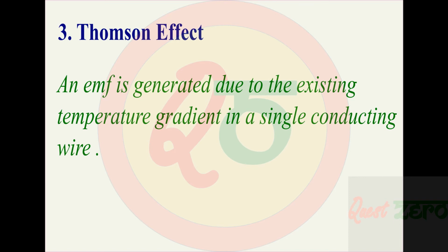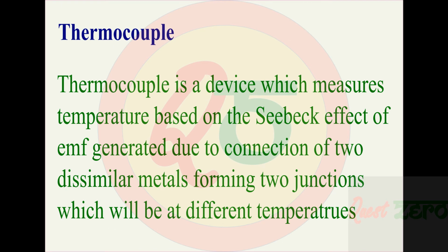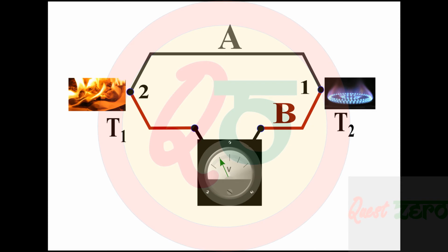Now we'll define what a thermocouple is. As we have spoken before, a thermocouple is a device which measures temperature, and it is based on the principle of the Seebeck effect, wherein the EMF is generated because of two dissimilar metals forming two different junctions, and those two junctions being at two different temperatures. If you look at the figure now, we take the same metal A and metal B as dissimilar metals joined to form junctions 1 and 2.